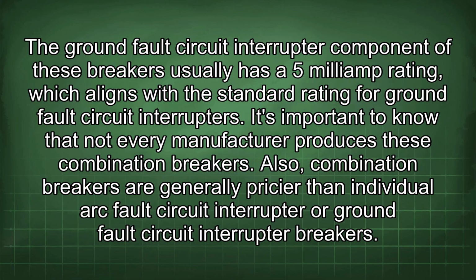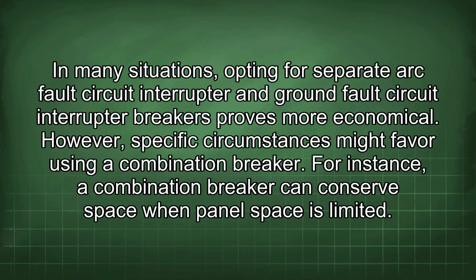Also, combination breakers are generally pricier than individual arc fault circuit interrupter or ground fault circuit interrupter breakers. In many situations, opting for separate arc fault circuit interrupter and ground fault circuit interrupter breakers proves more economical. However, specific circumstances might favor using a combination breaker. For instance, a combination breaker can conserve space when panel space is limited.